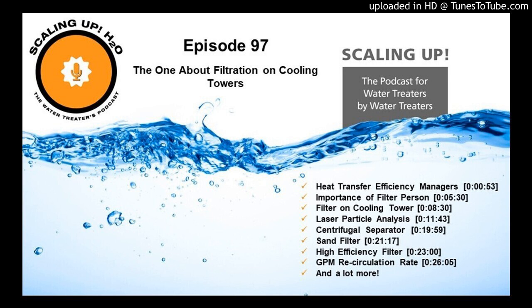If you use city water, or clean water, any kind of clean water into the cooling tower, traditional sand filtration should use the city water and pump that back through the filter to the drain to backwash it. So the only water you're using out of the cooling tower is maybe that little bit of water in the top of the tank when you go into backwash. So that would sound to me like a system that's set up to backwash with tower water.